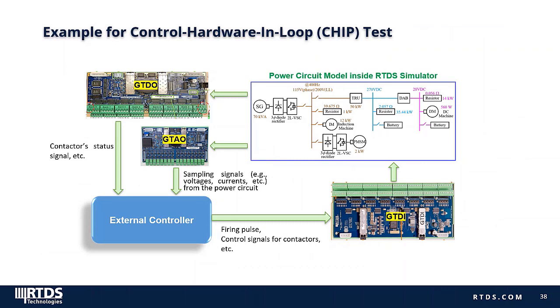Here is an example of what a control hardware-in-the-loop setup might look like. All power circuits are modeled inside the RTDS simulator. Sampling signals — for example, voltages and currents from the power circuit — are sent out via the GTAO card to the external controller. The external controller may also require contact status signals, which are read in via the GTDO card. After the control schemes execute in the external controller, firing pulses and other control signals for contactors or other devices are sent back to the RTDS via the GTDI card.